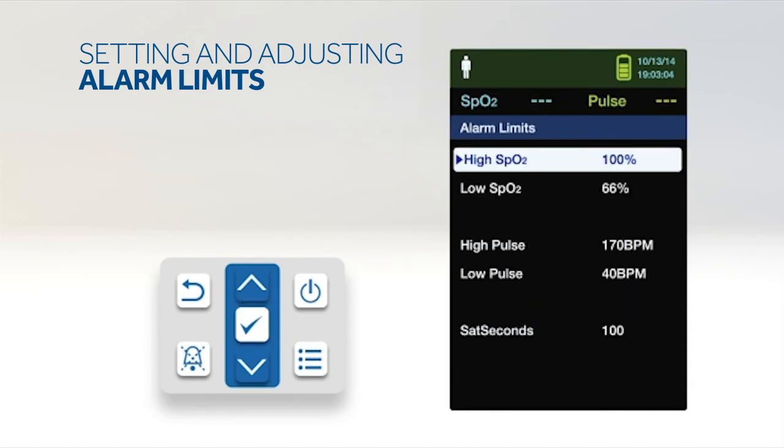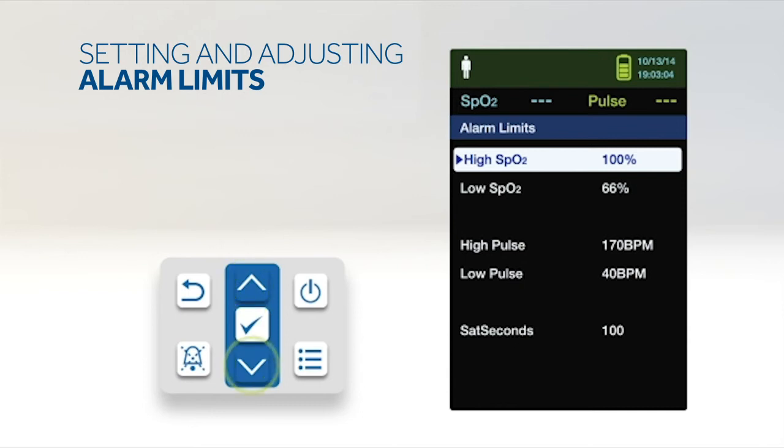Alarm settings include pulse rate and SPO2 alarm limit ranges, Nellcor SatSeconds option. Press the up or down button to highlight the desired option. Press the OK button to select the desired option.